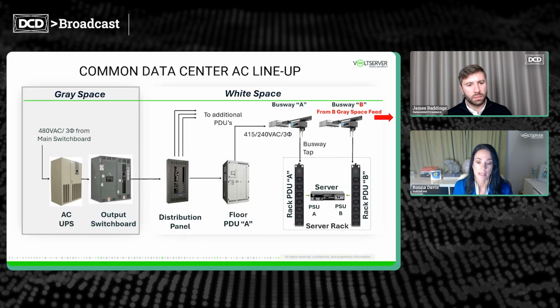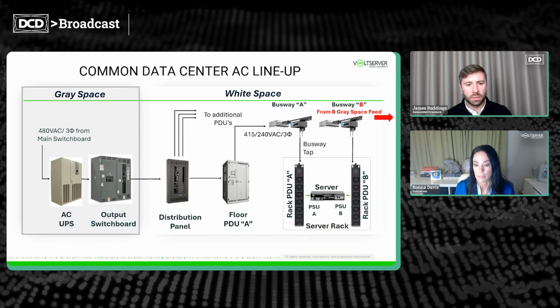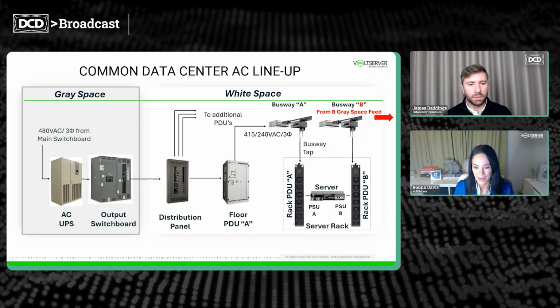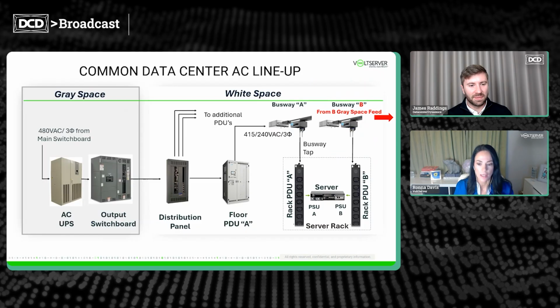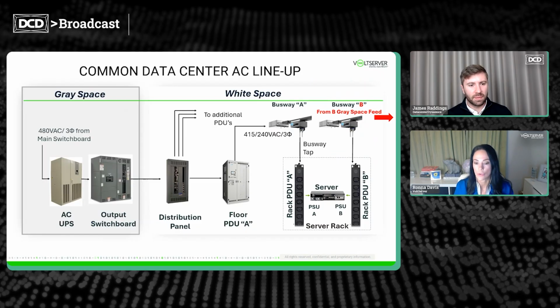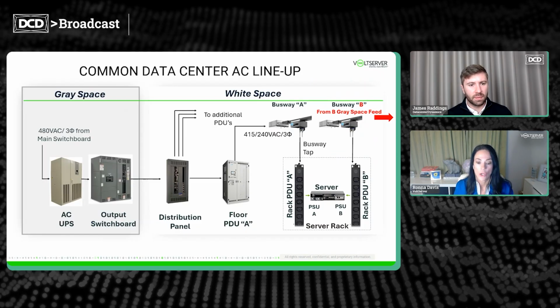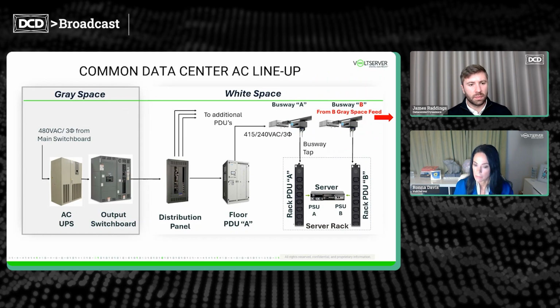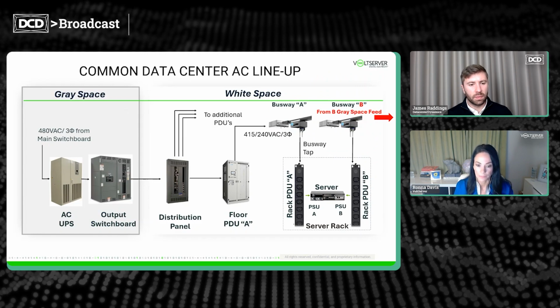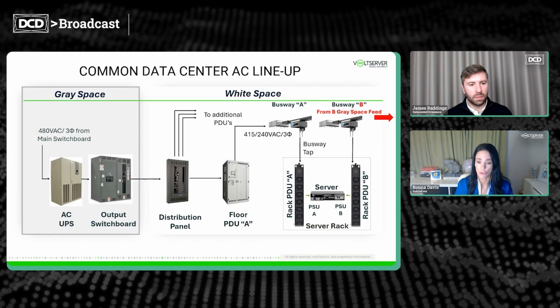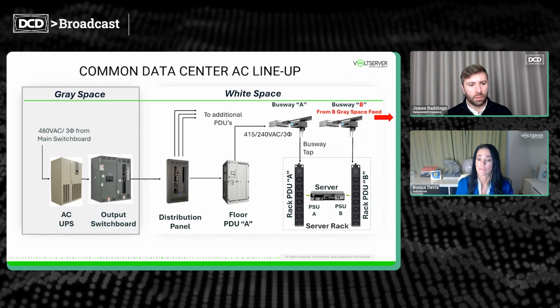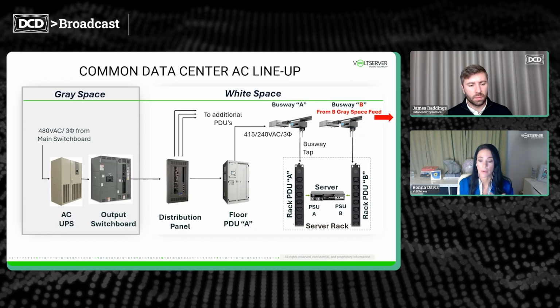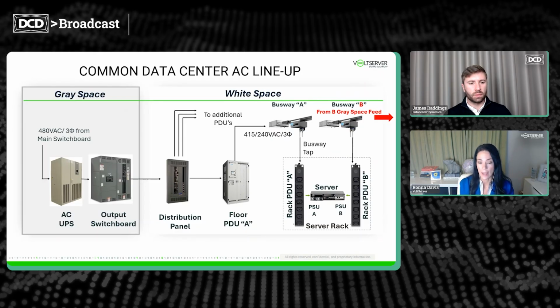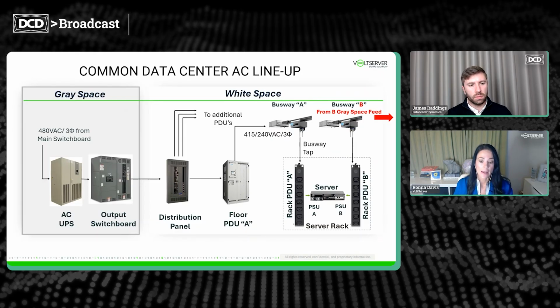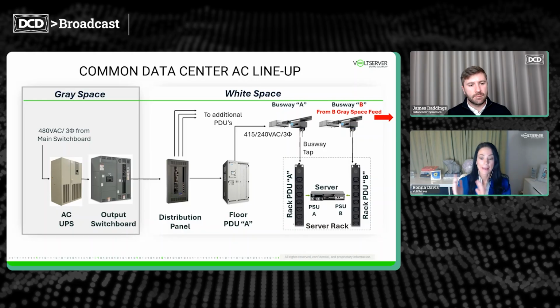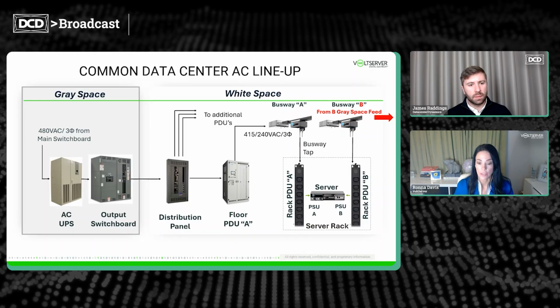Let's take a look at a standard AC 2N data center lineup. Probably looks pretty familiar to you, right? Maybe your lineup varies slightly, but in the gray space you typically have your main power entrance facility, your UPS, and main switchboard, sometimes with a static transfer switch. In the white space, you have distribution to the floor PDUs, and from the floor PDUs you have the busways, busway taps, and vertical server cabinet PDUs. You have that lineup for both the A and B sides of the 2N architecture.